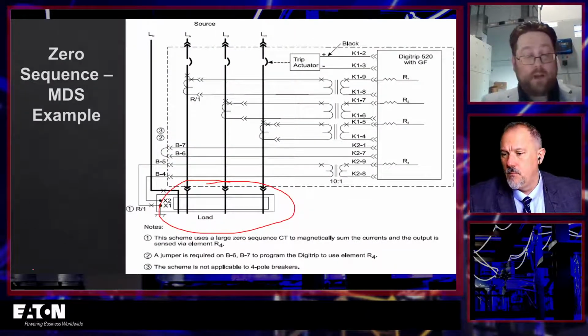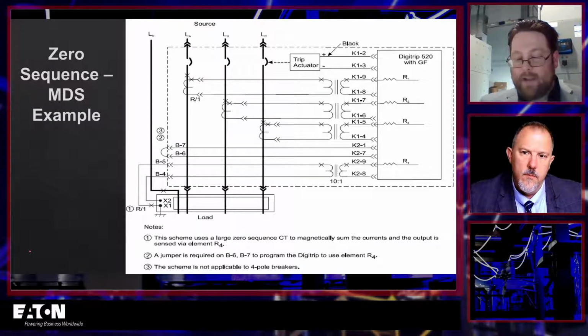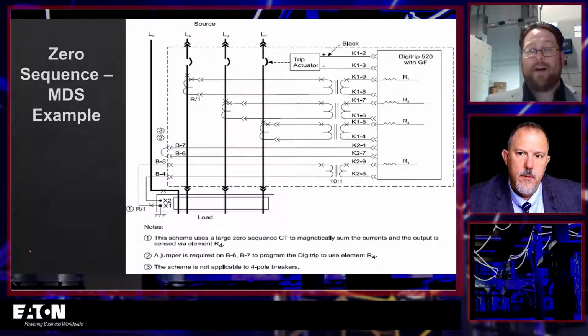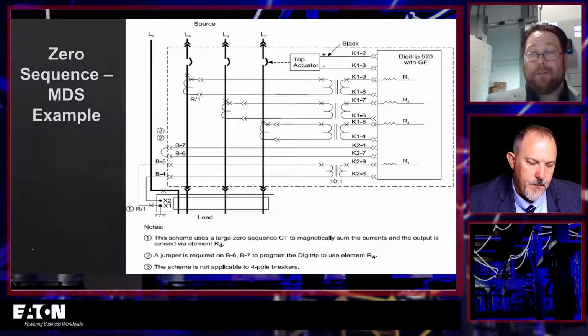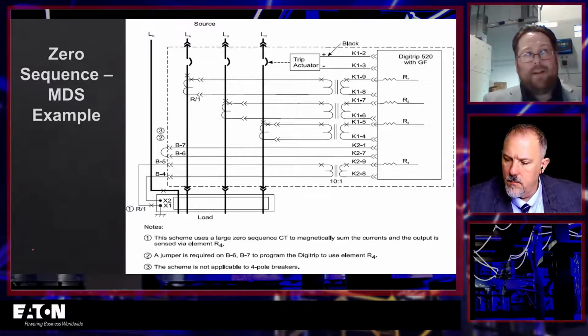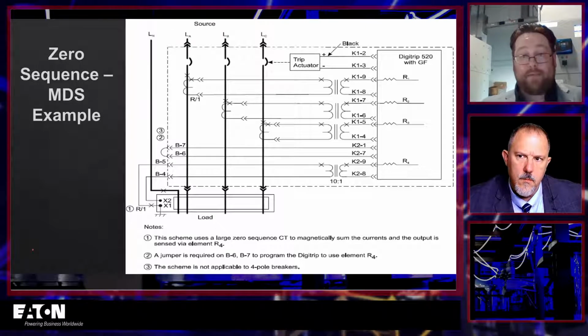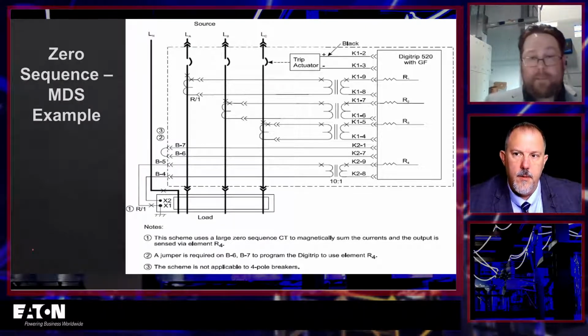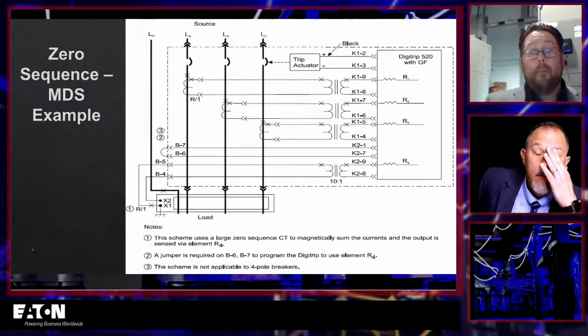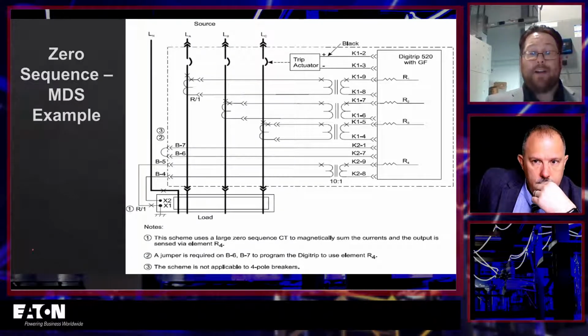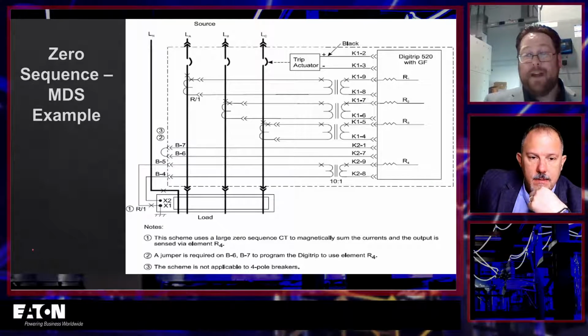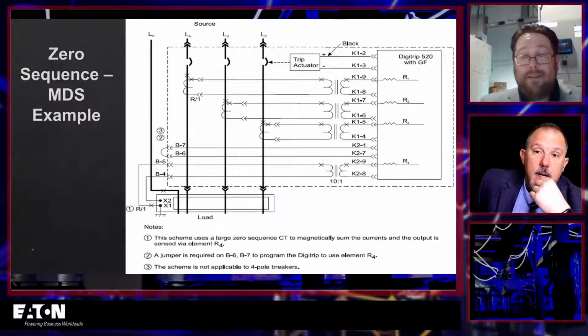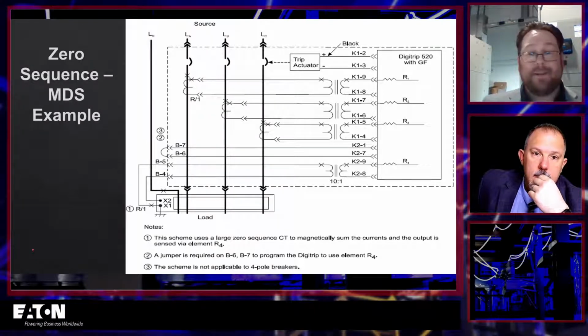Yes, and one of those other interesting things to be aware of is you're injecting lower currents, right? We've been talking about the 1,200 amp ground fault level, but we need to test high enough that we make sure that we are above that threshold, right? So generally, about 125% of pickup is what you're looking for, but if you're just injecting current through a zero sequence and one phase of a larger breaker, do you actually have enough ampacity to self power the trip unit? You might not in some cases, right? Because there's no actual power coming off of that neutral or zero sequence CT circuit.